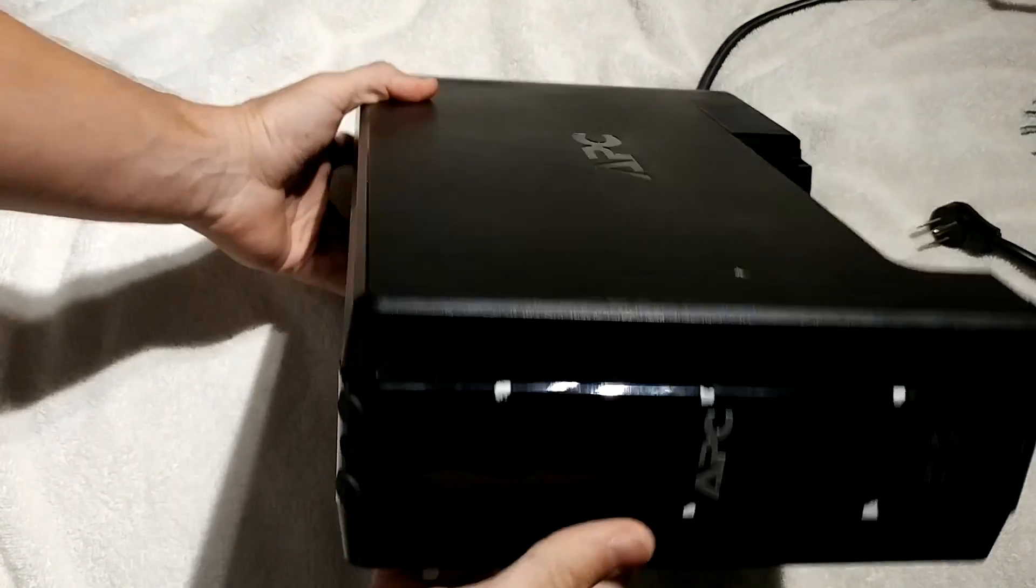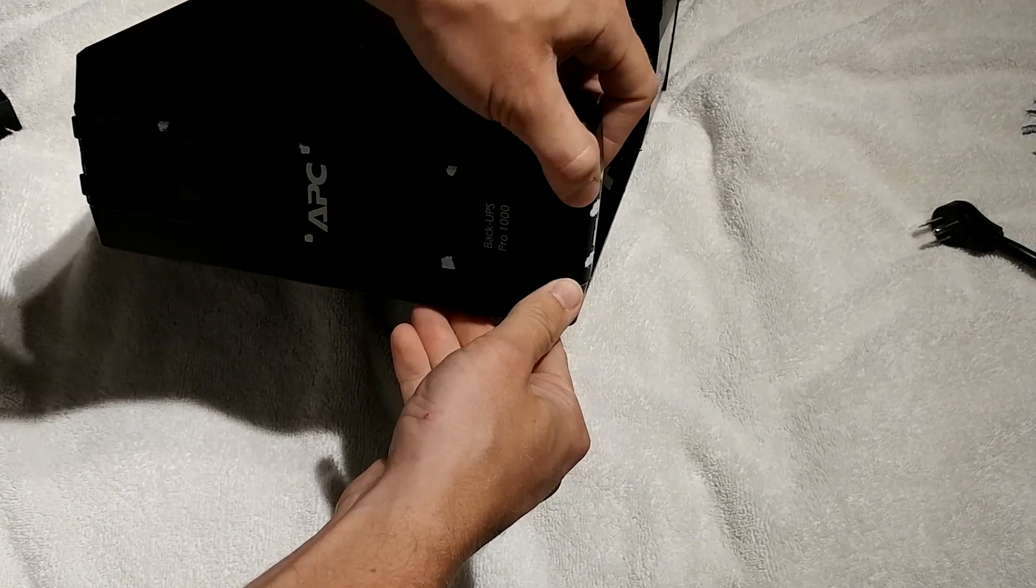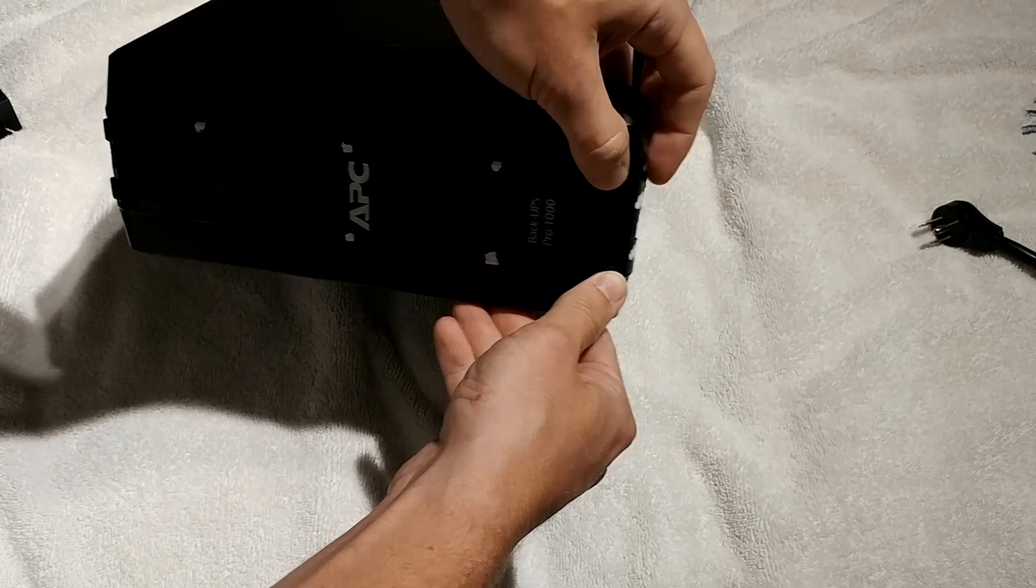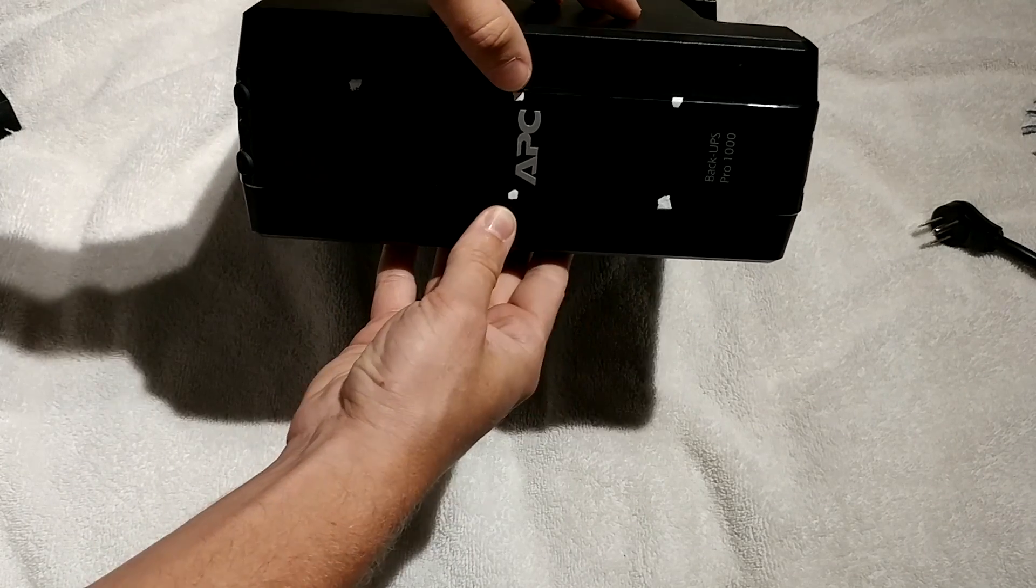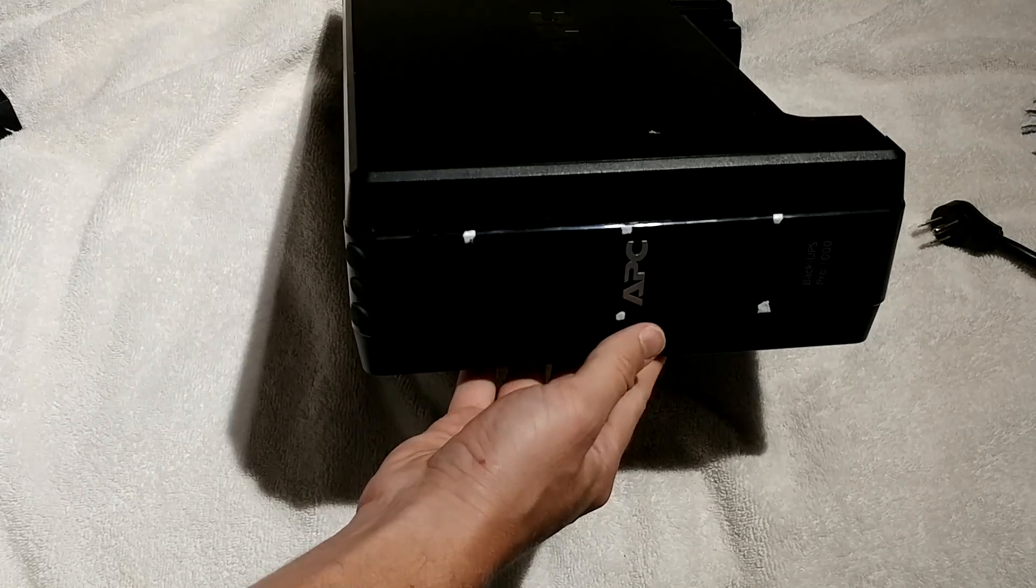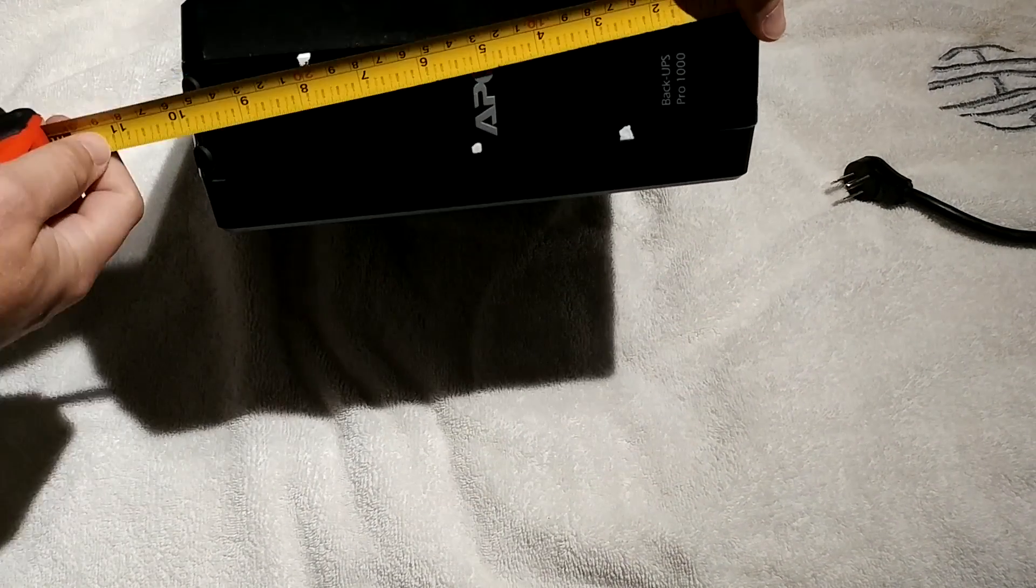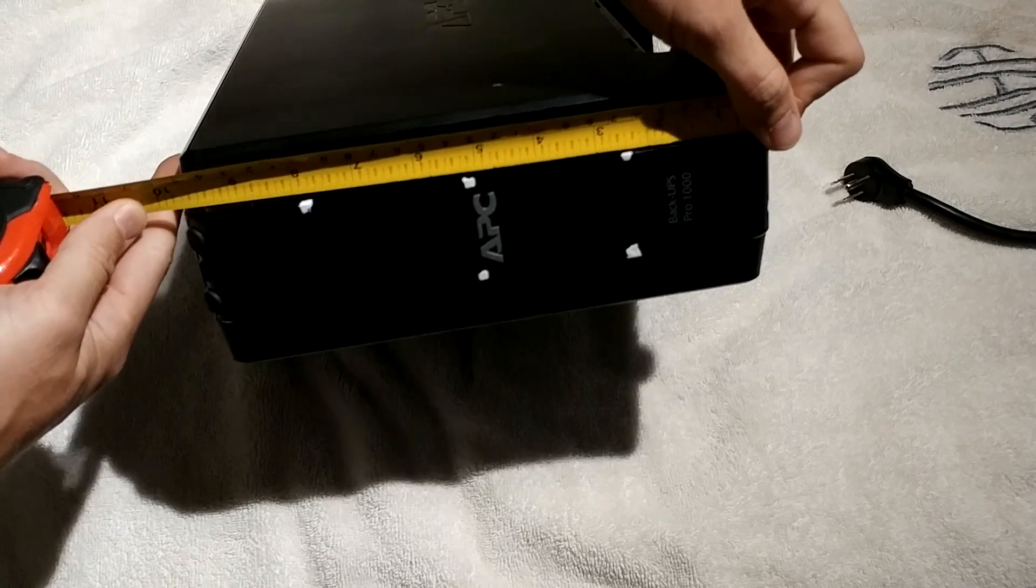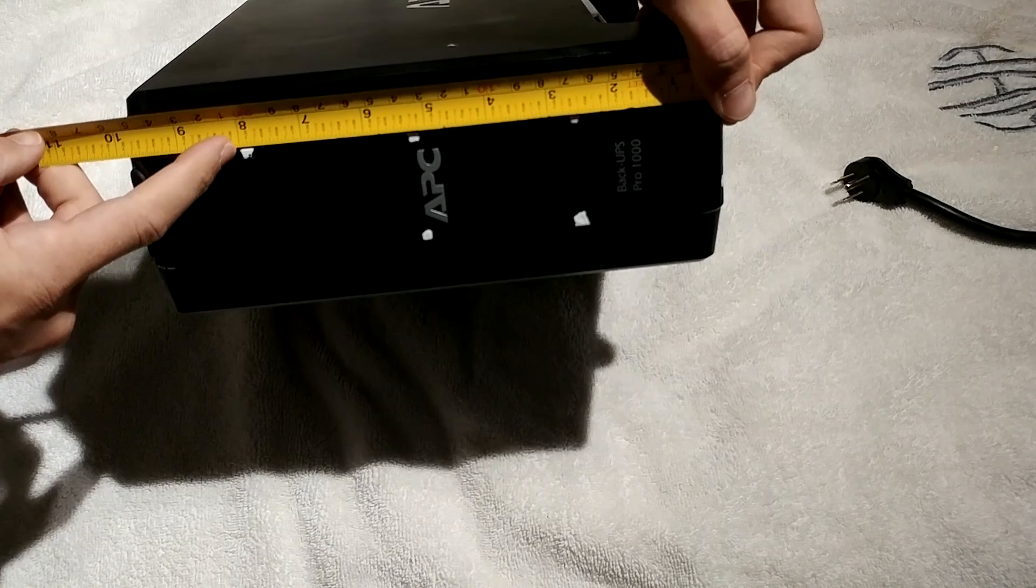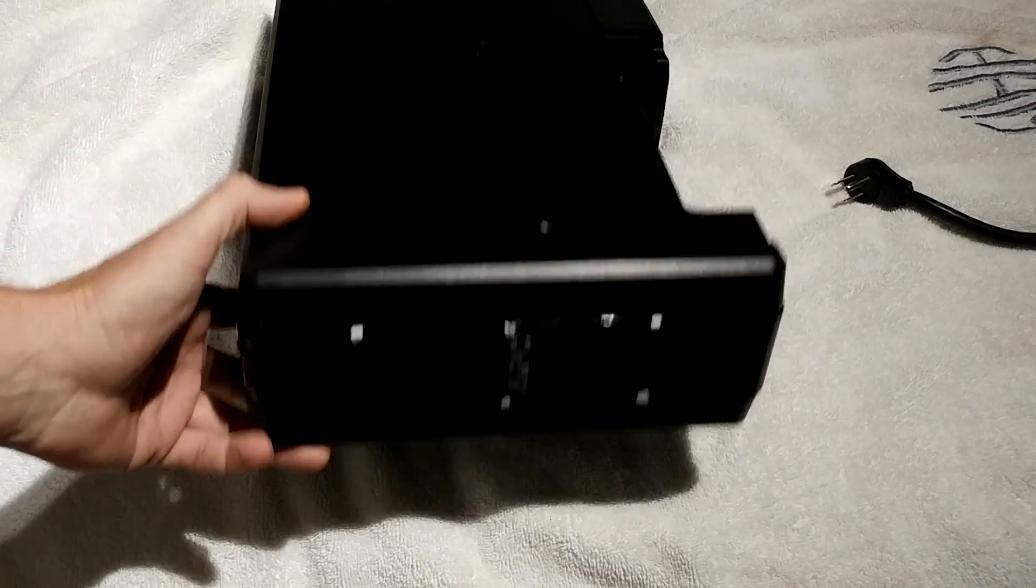What you're going to need for this is, I've pre-marked where there are those plastic catches, because I've taken this apart before. You're going to have to carefully pry these things up with a plastic pry bar. There's two on the bottom, two right up here right above the logo, two right here right next to APC, and then one up here. And then the whole thing should just kind of come up and out towards the top. From the bottom of the unit, about two and a half inches up from the bottom, there's some from about five and a quarter inches up from the bottom, there's the second pair. And then the last catch is right about here up at about eight inches from the bottom. Start with these two on the bottom, and then slowly pry this cover off.